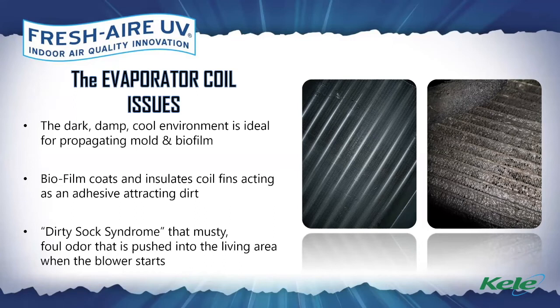You bring in a company to pressure wash or chemical clean, and almost immediately it starts up again. It's a vicious cycle. Now, of course, there is real dollars and cents here. I mean, it's costing a lot of resources to run a fouled coil, not to mention the microbial blow off and the odors, often called dirty sock syndrome, that musty, mildewy smell when the blower kicks in and pushes that odor out into the working or living area. It is a huge issue.